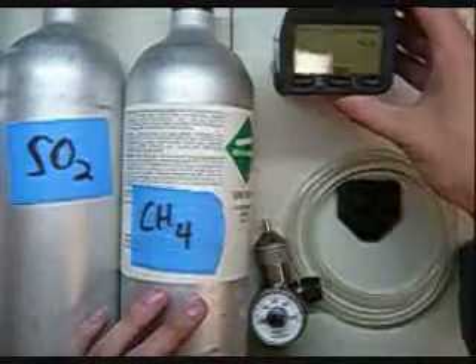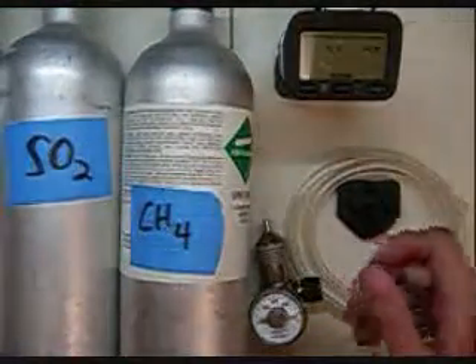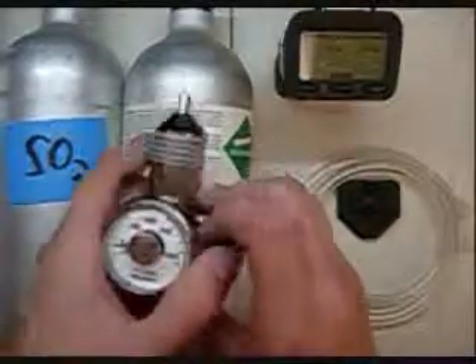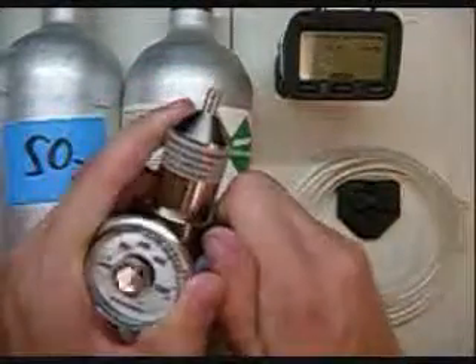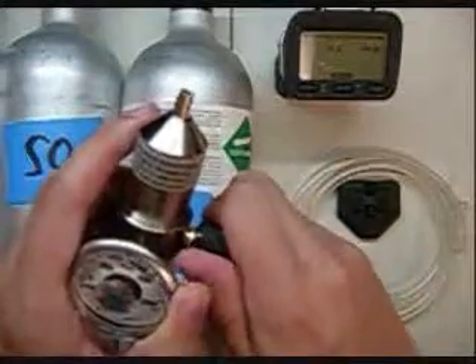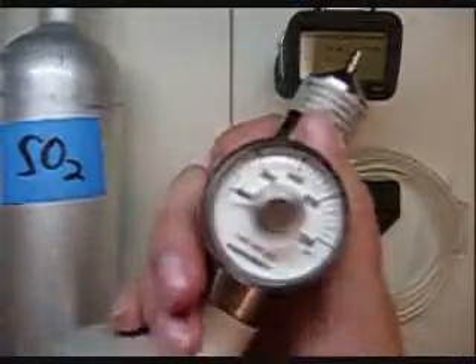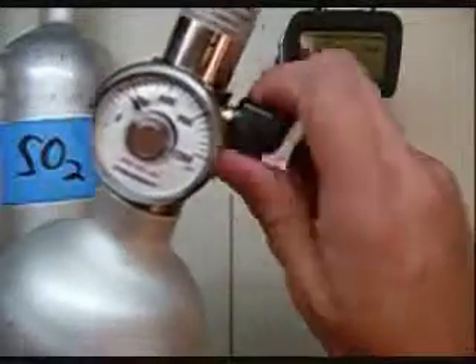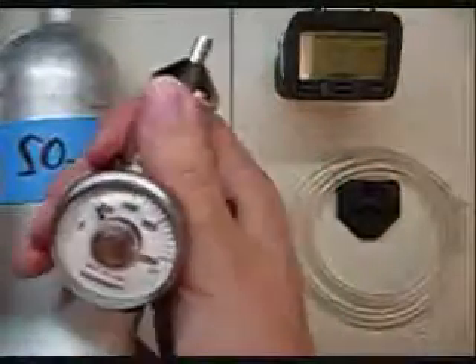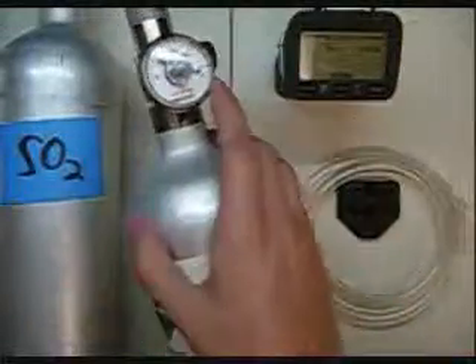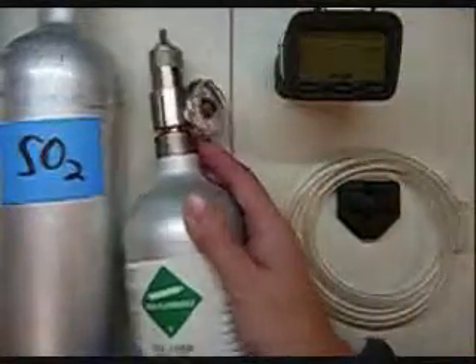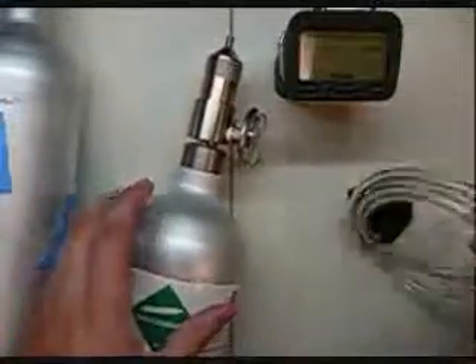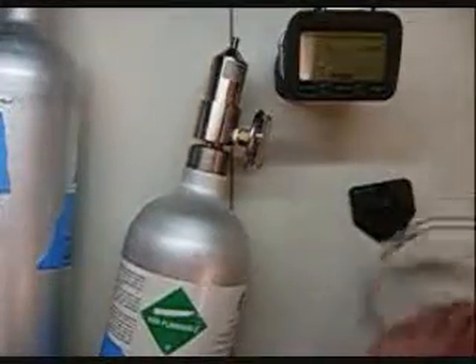Now while that's zeroing out, we can take a look at the other cylinders and how to get these prepped. First thing you're going to do is take your regulator. Now open the regulator. Never put a regulator into a cylinder if it's closed, it'll contaminate the cylinder. So once you hear gas flowing, go ahead and turn it off, and then continue putting the regulator on. Now take your tubing. Go ahead and attach it here.